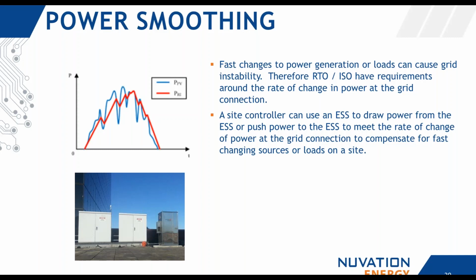It's a 7 kilowatt hour battery that essentially is to smooth out the rate of power change due to solar. The blue line in this graph is showing what's happening with the solar collection. These dips in the blue line are when maybe a cloud goes in front of the solar panels, leading to a very quick reduction in the amount of power being generated.